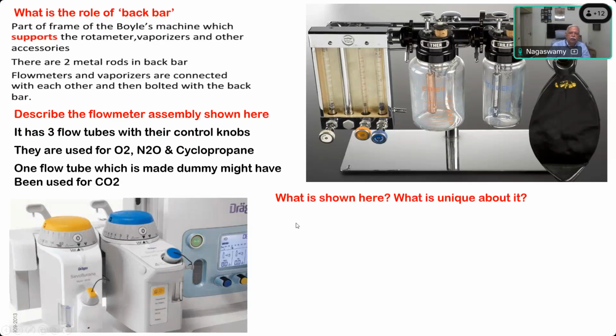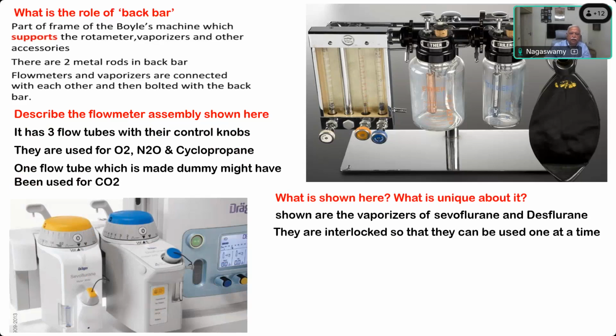What is shown here and what is unique about it? Anesthesia vaporizers. Vaporizer for desflurane and this sevoflurane vaporizer, modern vaporizers are there. But what is the peculiarity about it? They have interlocking. You can use the vaporizers for sevoflurane and desflurane, they are interlocked so that they can be used only one at a time. You can't use both. Why has this been incorporated? Next question I think comes. What is the purpose of interlocking and how was it in older models?